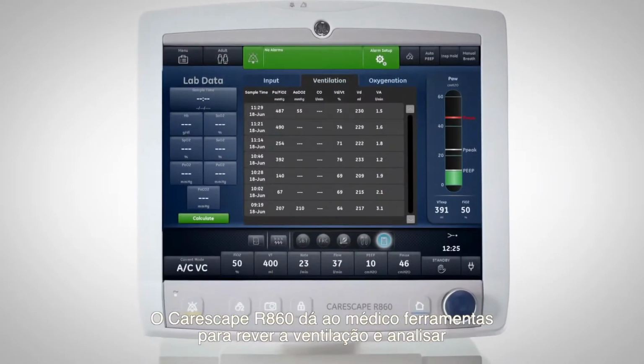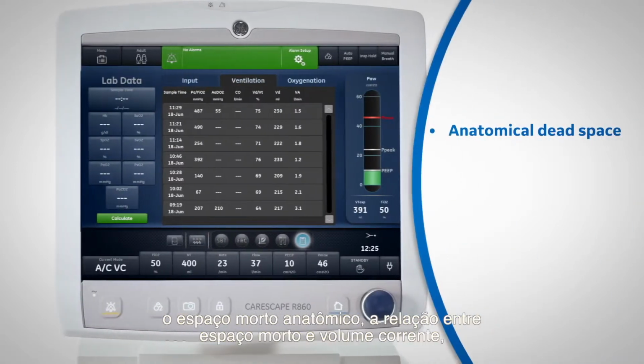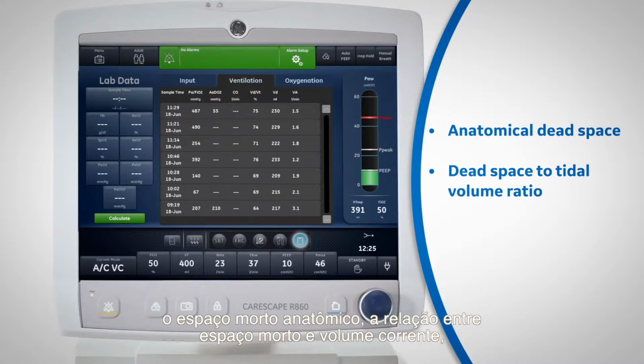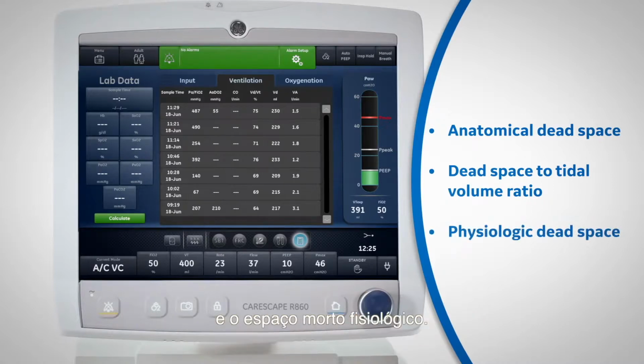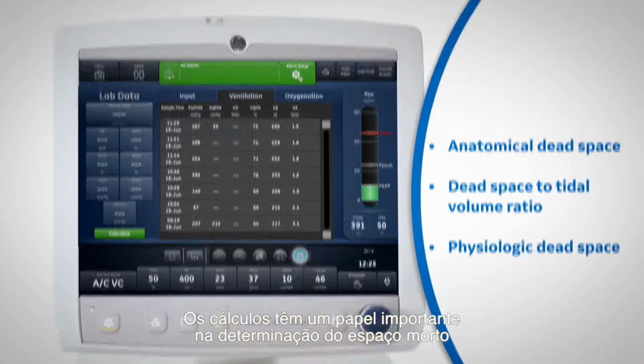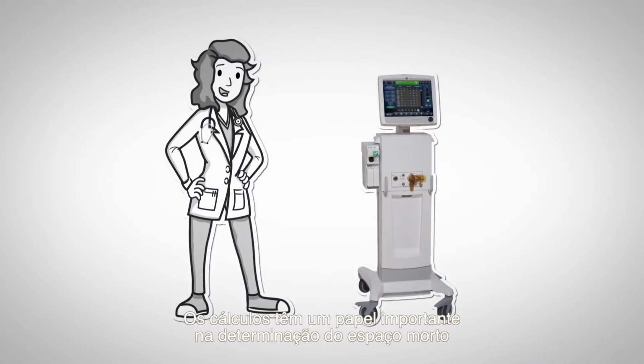The CareScape R860 gives the clinician the ability to review calculations to analyze anatomical dead space, dead space to tidal volume ratio, and physiologic dead space. Calculations play an important role in determining dead space and wasted ventilation from overextended alveoli, which help to provide the clinician an additional tool when setting tidal volume and PEEP.